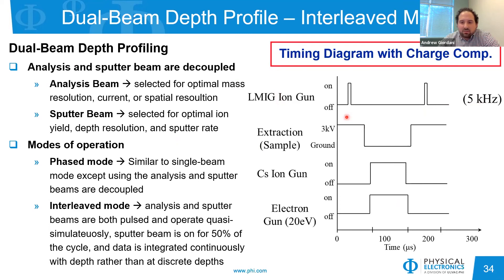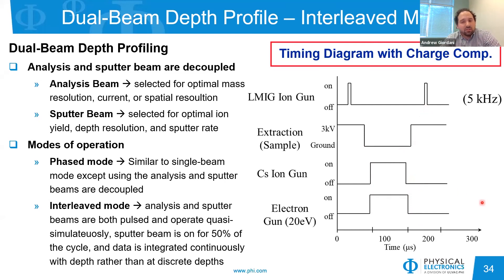Interleave mode is another type of dual beam depth profiling where both the sputter and analysis beams are pulsed, operating quasi-simultaneously. The sputter beam is on for 50% of the cycle. Charge compensation is still possible in interleave mode: using the timing diagram, the LMIG fires at 5 kHz, the sample is at high voltage for extraction, then during the flight time the sputter gun and electron gun are turned on for sputtering and charge compensation, then turned off before the next LMIG pulse. So insulating materials can be analyzed in interleave mode with high data point density.